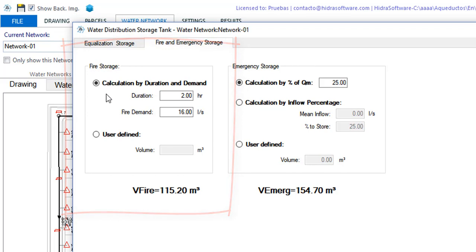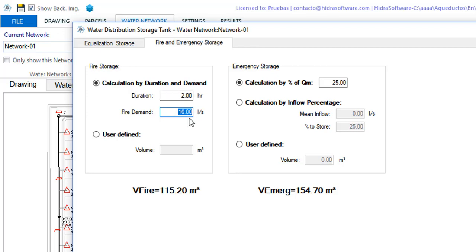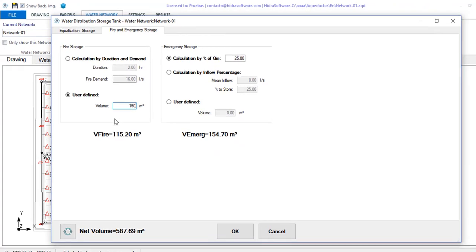In this specific case, we consider the option in which the applicable design code specifies a duration of the fire, which by default is of 2 hours in the software, as well as a fire demand or fire flow which, generally, is the same one that we used in the verification of the network at the most unfavorable hydrant. Here we have it at 16 liters per second. A variant is that you directly enter, by activating the second option, the fire storage volume.